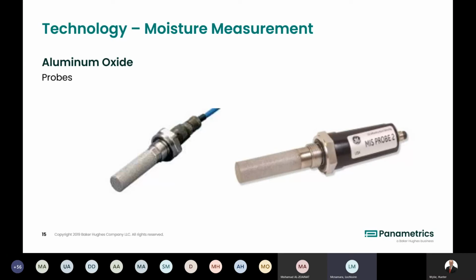In terms of the stabilization time, it does depend on a number of factors. The sensors themselves should be the same, but you have the length of tubing from your takeoff point to the sample system, and how complex your sample system is. A well-designed sample system is very important here, so that you don't have dead legs or other moisture traps in the system, because most of you are going to be measuring moisture at very, very low levels. We're talking less than 1 ppm, less than 5 ppm. So any moisture trapped in a system is going to affect the sensor over time, because it's included in the moisture measurement.